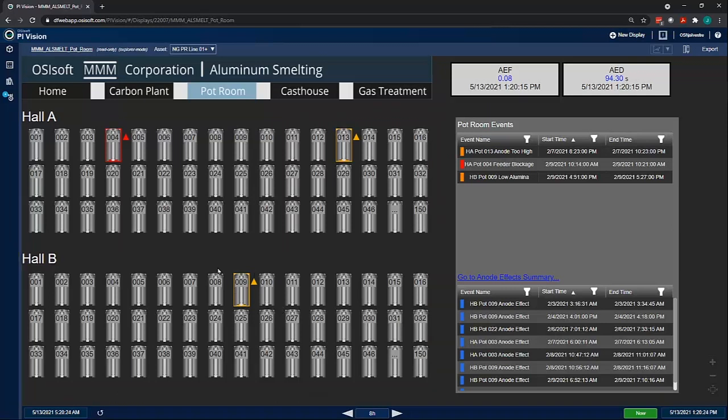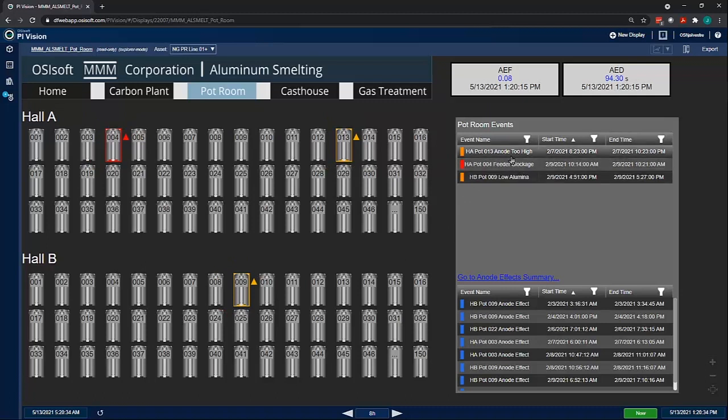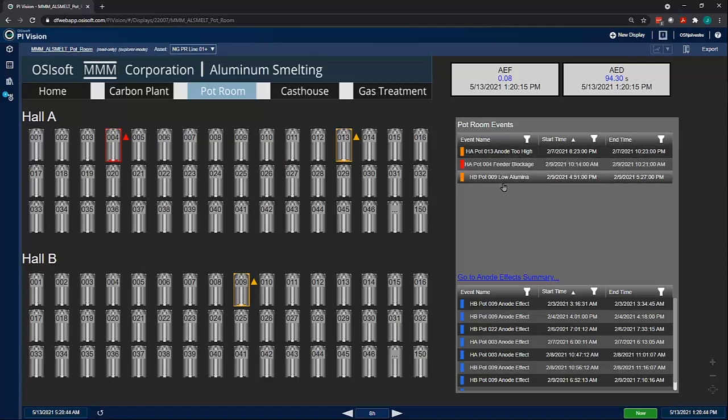Here I quickly see that there is an issue with pot 4, pot 13, and pot 9. With pot 4, it is experiencing a feeder blockage. Pot 13 has an anode that's positioned too high, whereas pot 9 has low alumina.